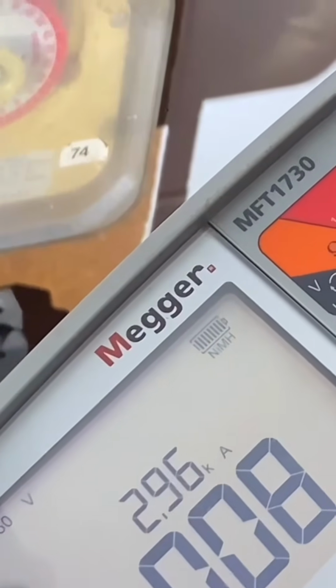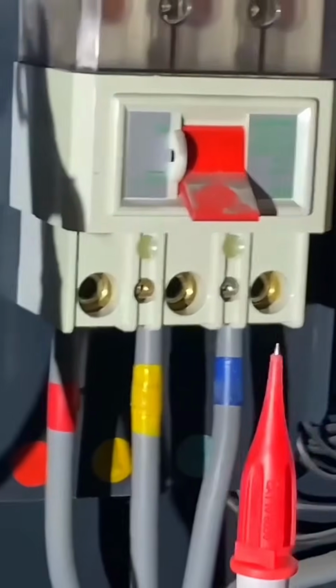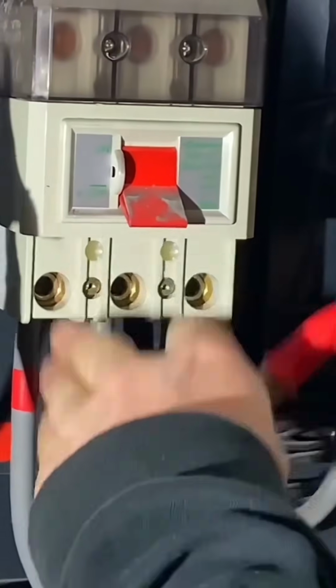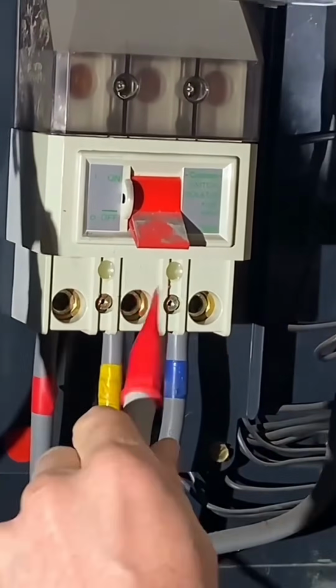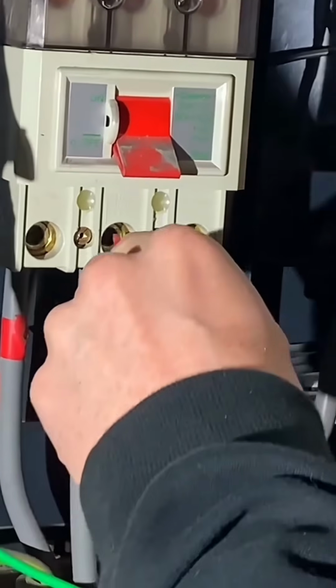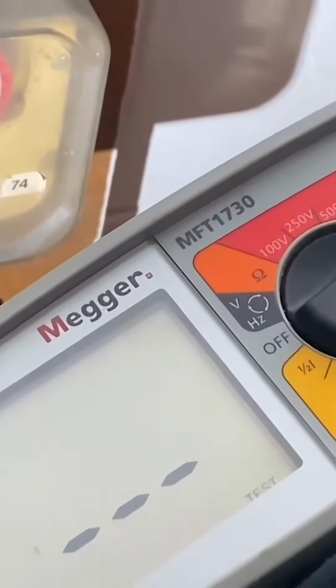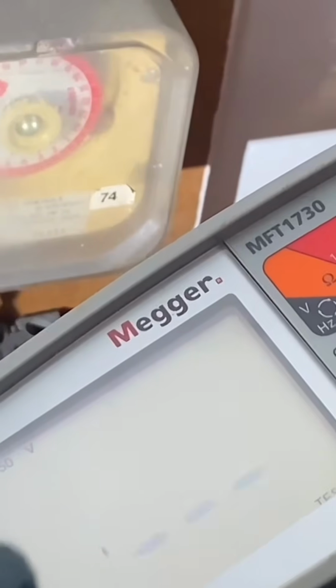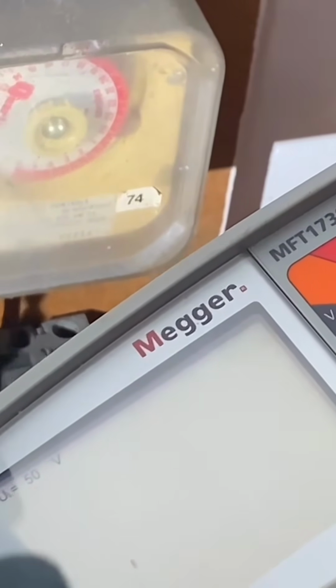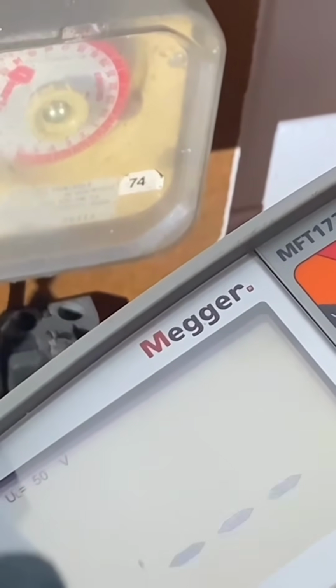So as you can see there, that's it, we're finished, pack up and we're ready to go. Is that right, Matt? No, so that's on one of the phases, so obviously there's 3 phases, so we'll just repeat that same process on the next phase. So again, because we're going between neutral and the phase, it's detecting a single phase voltage, so I think it's about 240 volts in here.